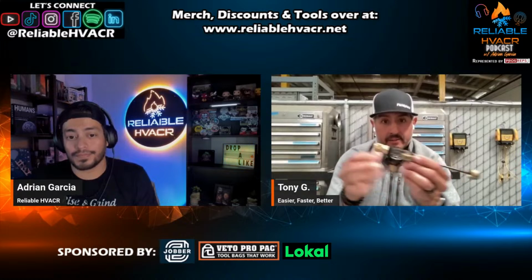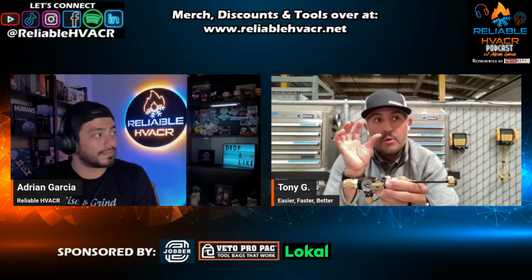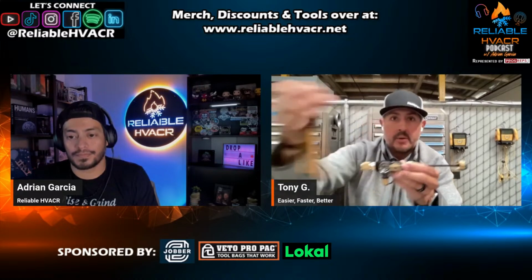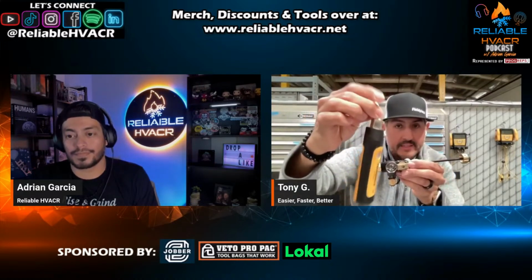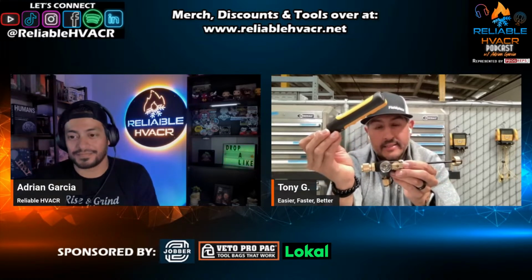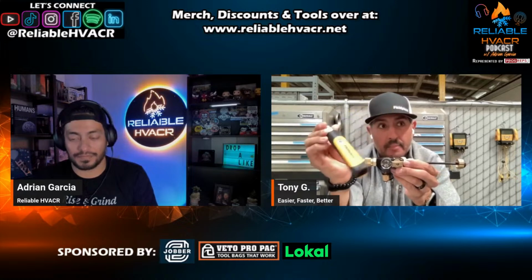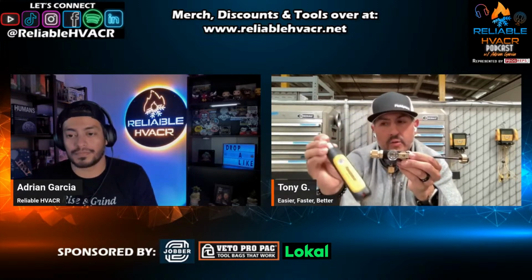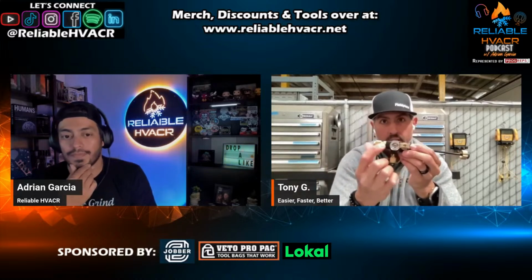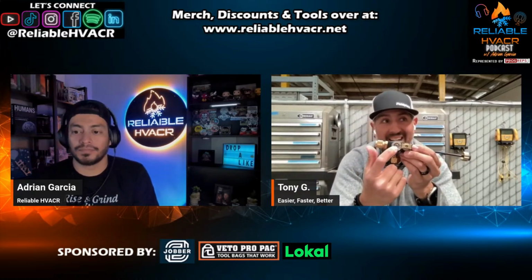In addition to that, a lot of people have moved towards wireless probes, right? Job link probes to measure pressures and things like that. These don't necessarily have a sight glass. So unless you're putting your own sight glass somewhere in the setup, we've kind of lost the ability to visually see the refrigerant. So in addition to seeing the valve core, this sight glass serves the function as a sight glass in a manifold. You can see the condition of the refrigerant when you're recovering or charging.